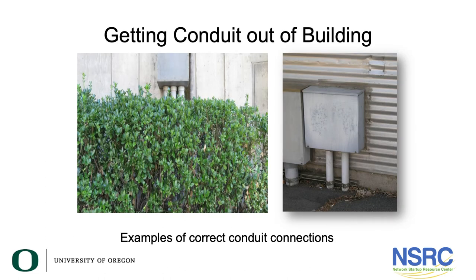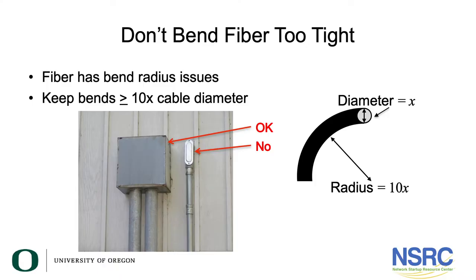Getting conduit in and out of a building: it's important that you enter a building in such a way that you don't allow rodents or water to get in. These are weatherproof boxes placed on the side of the building, with a hole drilled out the back for the cable to enter. This also counts as a pull point — you can remove the lid, pull on the conductor, and then route it inside the building.